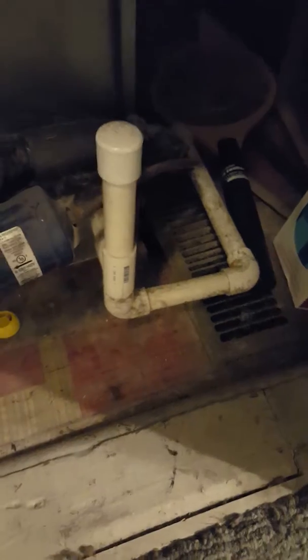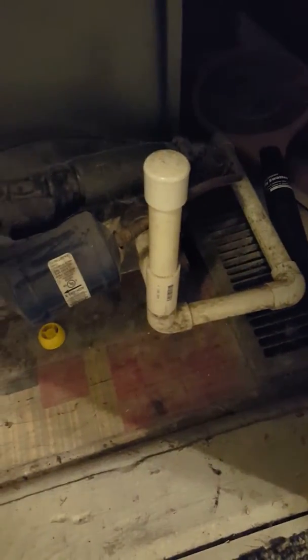Got a half-inch gas line coming in. It does have a side handle valve down there near the floor and an electric shutoff here. We've got a three-eighths, five-eighths suction liquid line that goes down through the crawl space.